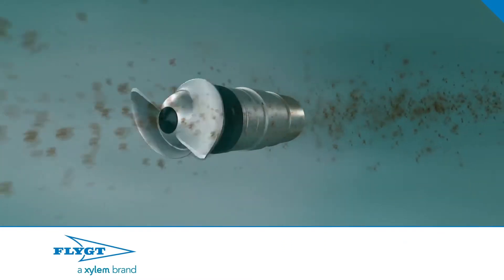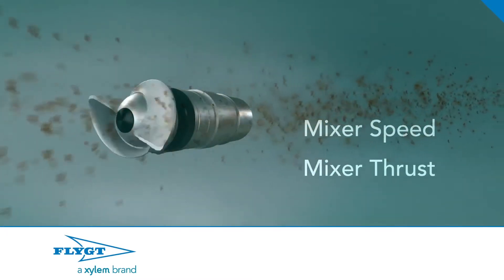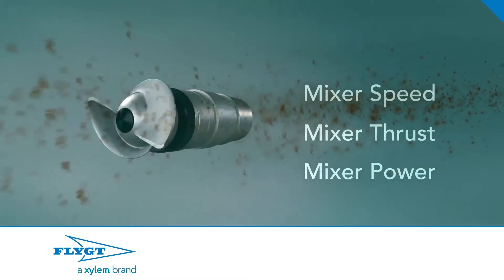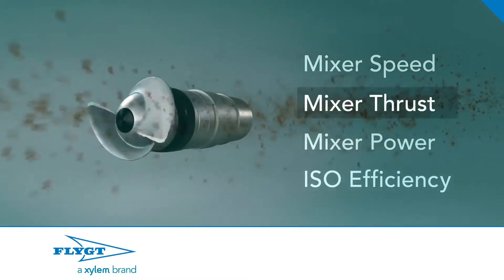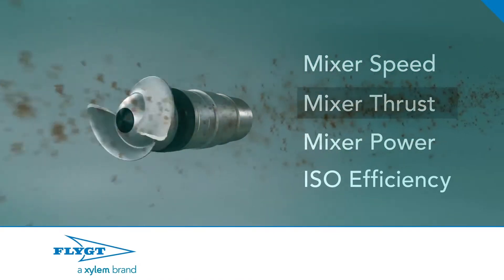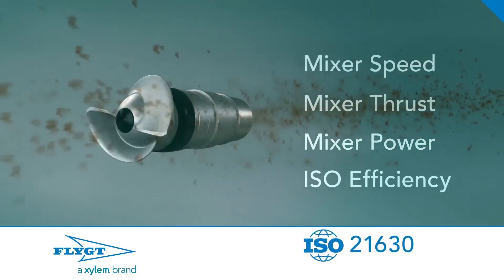To help determine the appropriate mixer, you should look at three key parameters: mixer speed, the thrust it is generating, and the power it is consuming to generate that thrust. This information tells you how hard the mixer is working, how efficiently it is delivering the needed thrust, and of course, what it is costing in energy consumption.